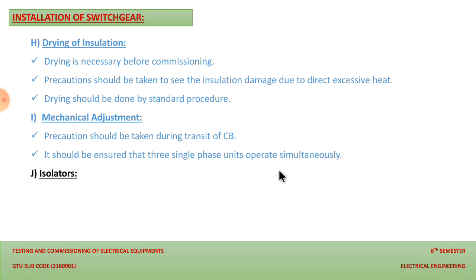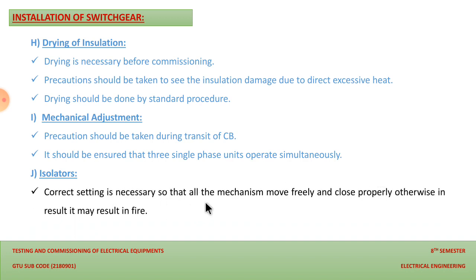Then the isolators are required to disconnect our switch gears from the system. So we need to check the isolator operation while we are installing our switch gear. Correct setting is necessary so that the mechanism moves freely. Isolator basically we operate manually as well as automatically. So we need to check all the moving parts of the isolator before we use our switch gears for the installation. The isolator is a part of switchgear, so we need to check that the movement of the isolator closes properly, otherwise it may result in fire, because a heavy spark will be produced between the contacts of the moving mechanism. So we need to check the operation of the isolator.